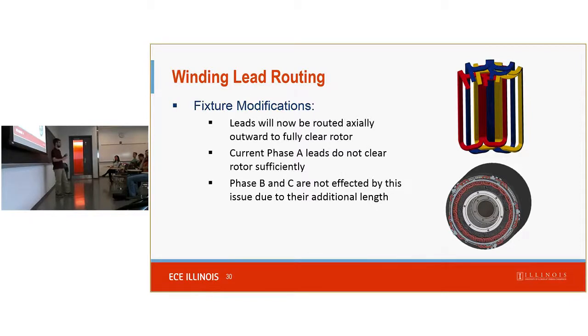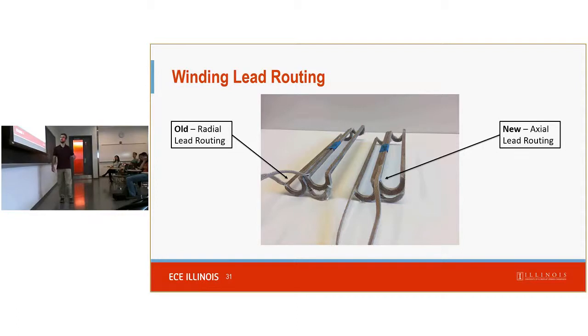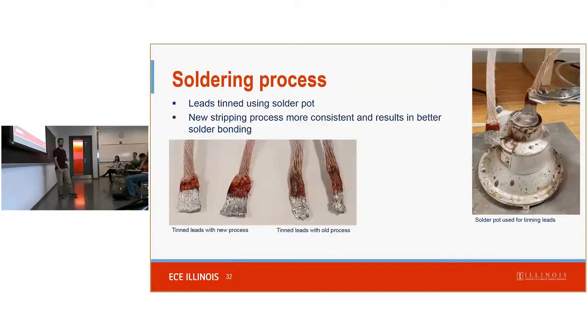Some things we changed were just to improve efficiency and make it go faster. Other issues were integration with the rest of the motor. In order to connect this, we have to have leads that come outside of the motor. And one issue we faced and fixed was that those leads, initially, were bending out in this direction, and that, in fact, was going to hit the rotor. And that's no good. If your rotor is scraping off your leads, your motor will not run for very many minutes before it stops working entirely. And so we redesigned the fixture just slightly to allow the leads to come straight out the end, and that prevents interference with the rotor.